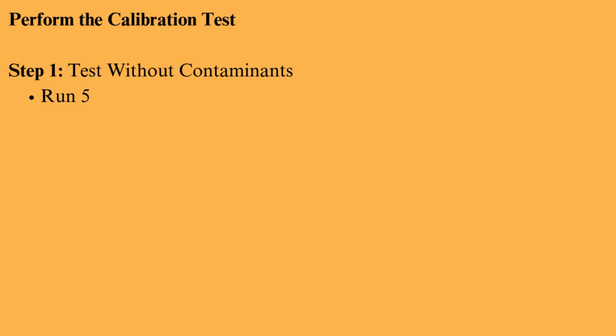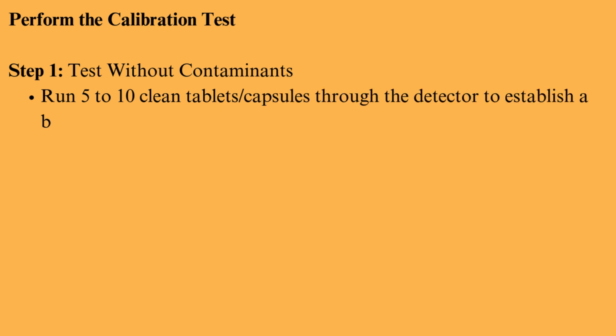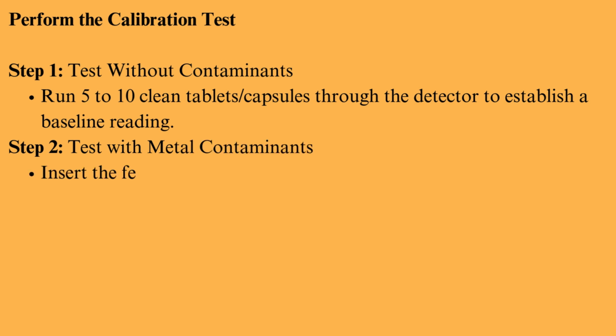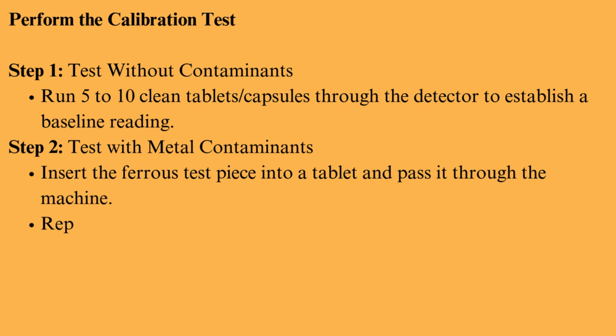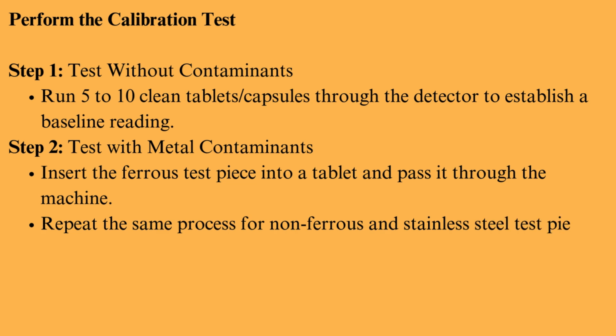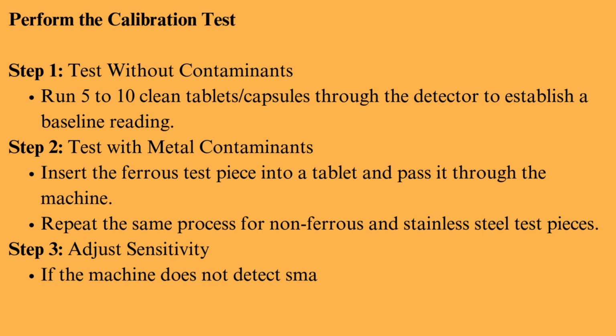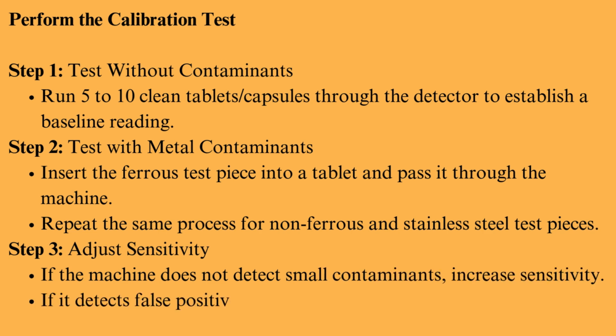Test without contaminants. Run 5 to 10 clean tablets or capsules through the detector to establish a baseline reading. Step 2. Test with metal contaminants. Insert the ferrous test piece into a tablet and pass it through the machine. Repeat the same process for non-ferrous and stainless steel test pieces. Step 3. Adjust sensitivity. If the machine does not detect small contaminants, increase sensitivity. If it detects false positives, lower sensitivity slightly to reduce noise.